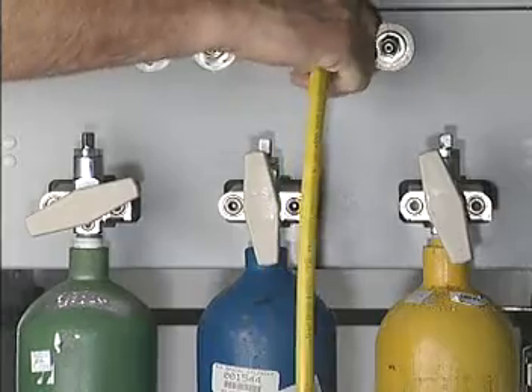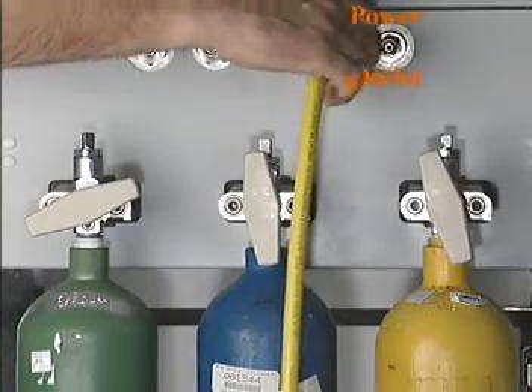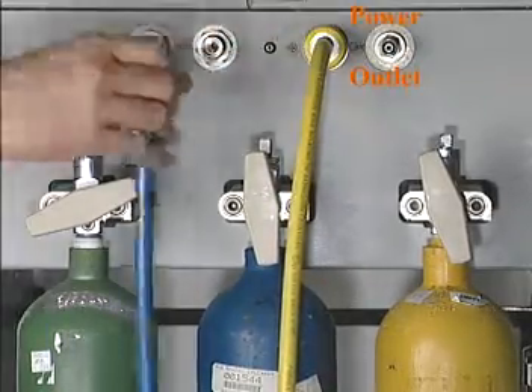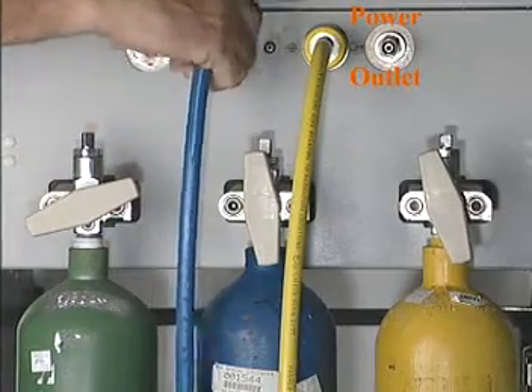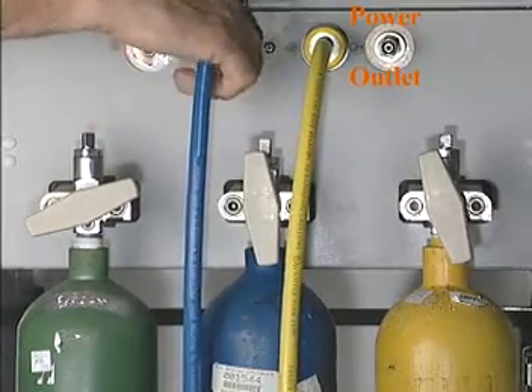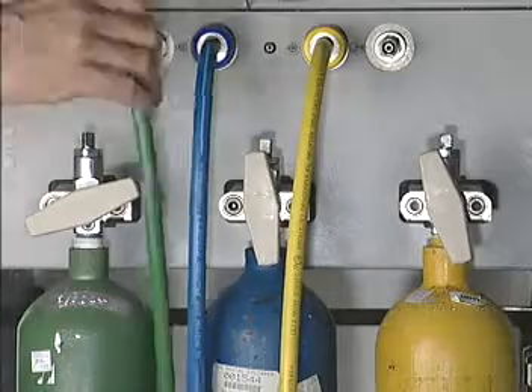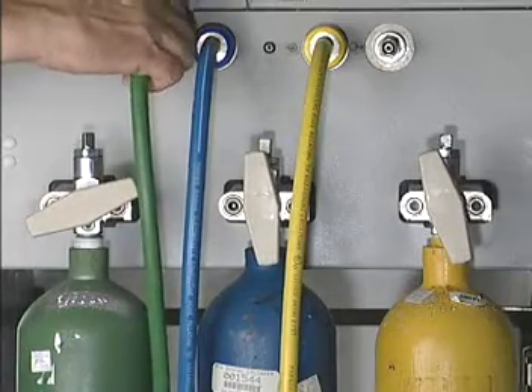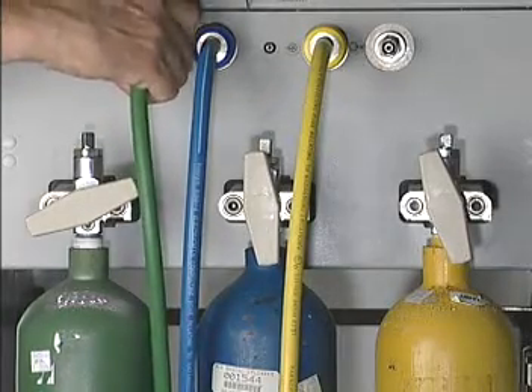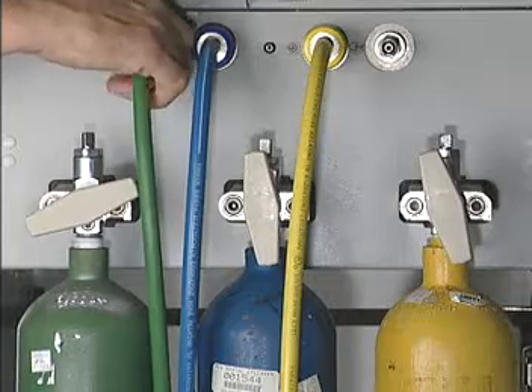DISS pipeline inlets are located above the cylinder yokes, and an optional DISS O2 power outlet can be located adjacent to them. Do not use the power outlet fitting as an inlet, as no O2 pressure will be indicated on the pipeline gauge on the front of the machine.